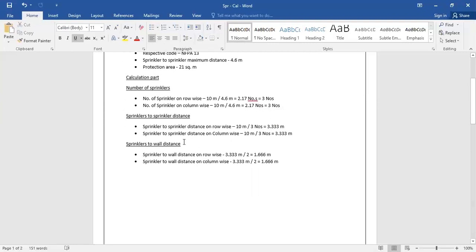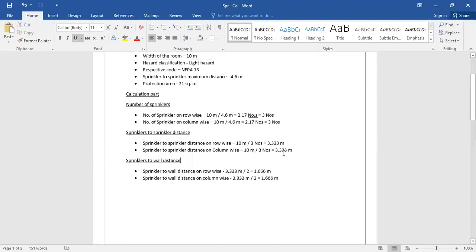The third part is the sprinkler-to-wall distance, also consisting of two steps. The sprinkler-to-wall distance is simply half of the sprinkler-to-sprinkler distance. Row-wise: 3.333 divided by 2 equals 1.666 meters. Column-wise: 3.333 divided by 2 also equals 1.666 meters.